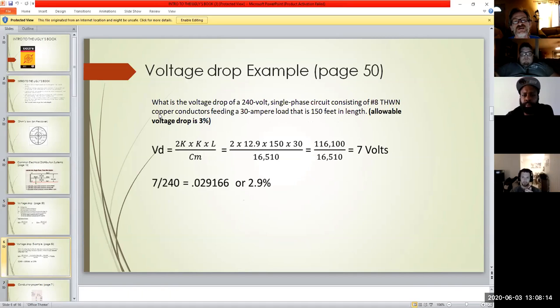Here's an example: figuring out the voltage drop for a 240 single phase circuit using number 8 THWN wire, which is rated for outside use since the W stands for wet. I want to deliver 30 amps over 150 feet. Punching it all through, we see how much loss I would have—running 240, I'm going to lose 7 volts altogether.